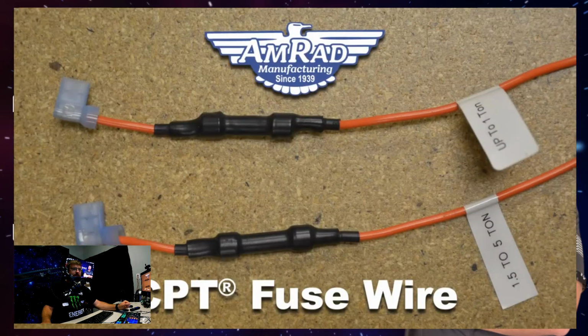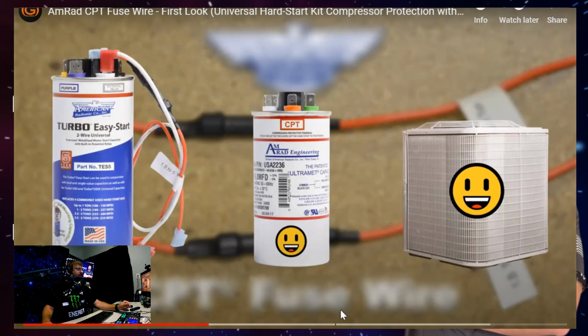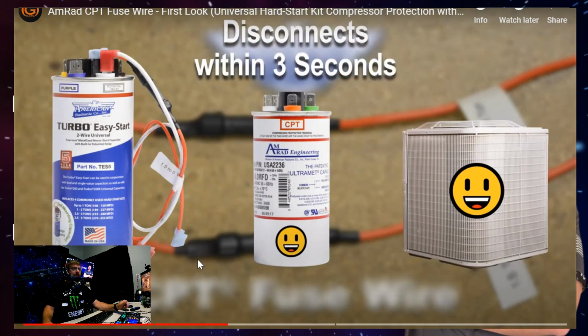Total failure. Amrad's newest innovation, the CPT fuse wire, prevents damage when a relay fails like this. If the relay becomes stuck with the CPT fuse wire attached, the fuse inside the... So this is kind of why I like our product. They have that built-in fuse protection, and their capacitors that they use for their run capacitors have that built-in CPT terminal right here that comes in handy. It's got a compressor protect terminal, so heaven forbid that relay sticks. Hey, it's going to protect it and not let the compressor keep running. Next, cutting off the motor start capacitor from the AC system within 3 seconds. No extra damage, no mess, easy replacement.